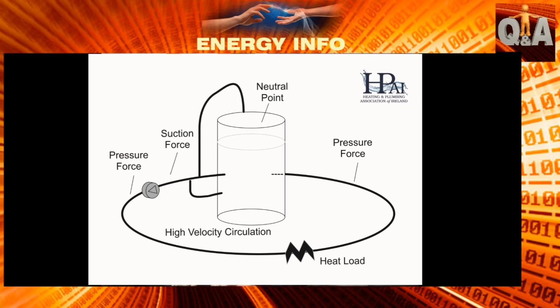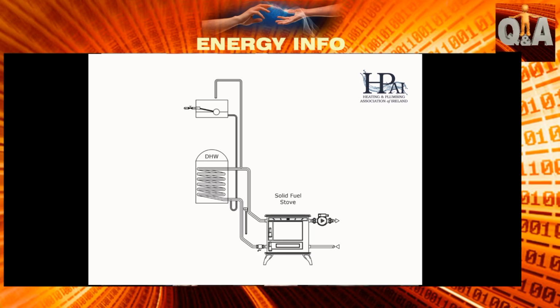If we look at a standard central heating appliance, a standard solid fuel stove, could be a cooker or a back boiler, let's think about the barrel for a second. The water on the top of the tank is the barrel. The expansion in that situation is on a neutral point because there's no pump, by using 4 pipes off the barrel. So any hot water rising meets the coil, the water in the cylinder cools the coil, the water gets heavier, falls down and back to the stove.